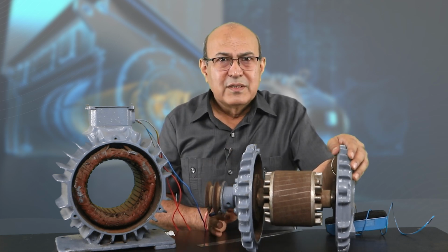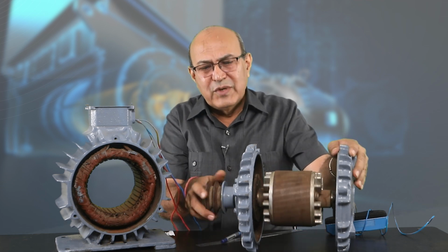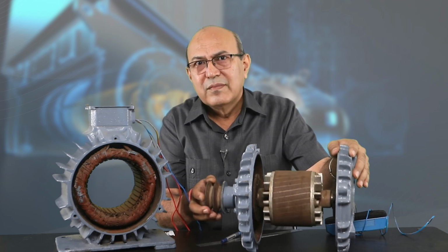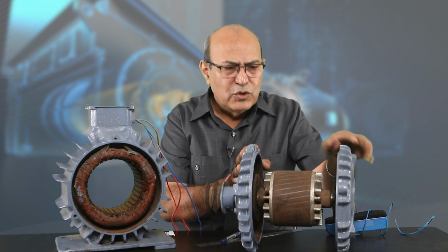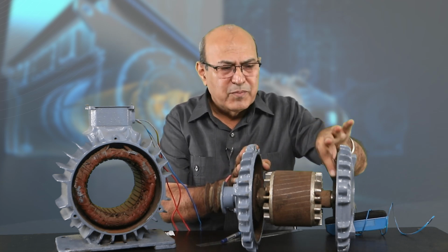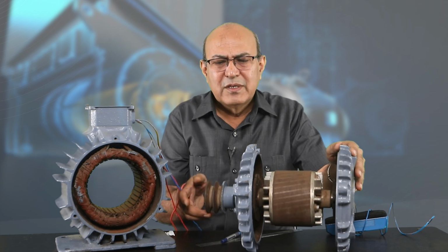And in maintenance, this is one of the common problems. If after applying proper supply, your machine is not rotating, what to do? Just try to rotate the shaft, whether it is free or jammed. If it is not free, then there is no electrical fault. It is some mechanical fault. You have to just open it, properly lubricate and remove the jamming, and it will start rotating freely.